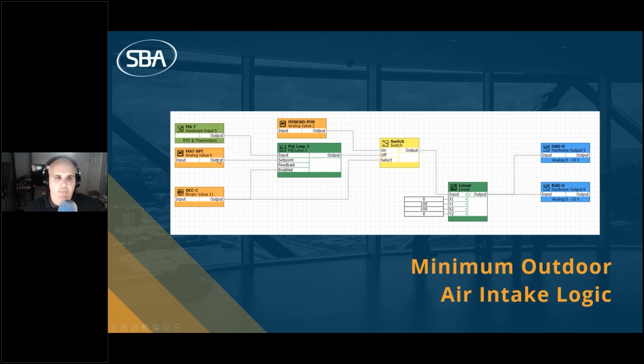So you'll see we have a mixed air temp and mixed air temp set point. And what that's going to do right here is take this right here, and I actually realize I have a code error in this. As I read it, I'm like, oh, that doesn't work. That switch should actually be somewhere else. But whatever, I could draw on it while I do this. But what would happen is mixed air temp going into the PID loop and mixed air temp set point, and then an occupied command. And oh, no. Yeah, it is wrong. I would have to put a maximum block right here, but whatever.